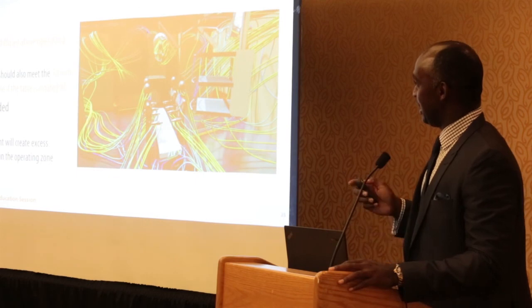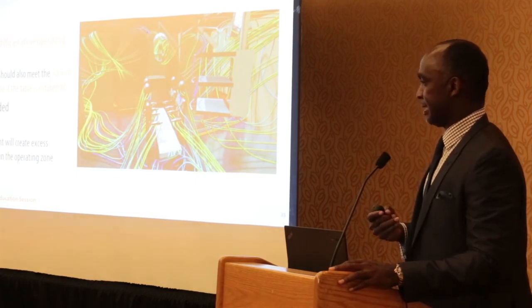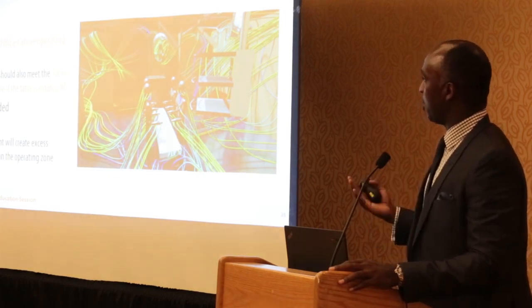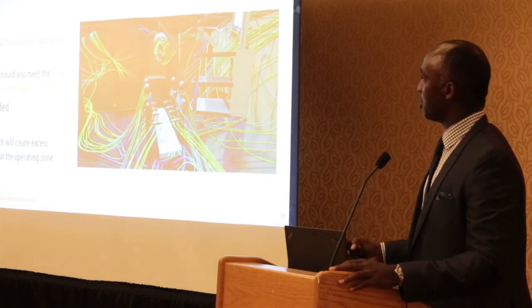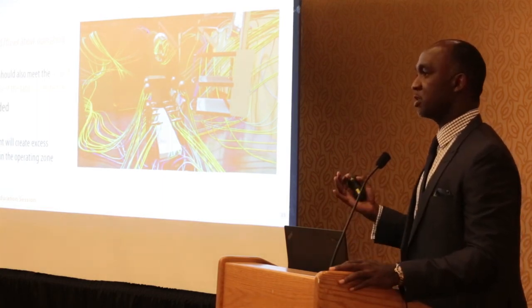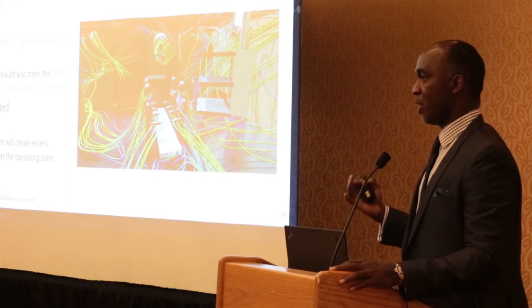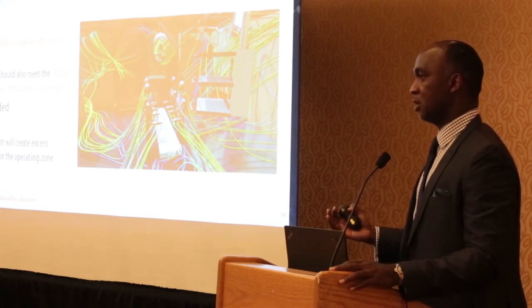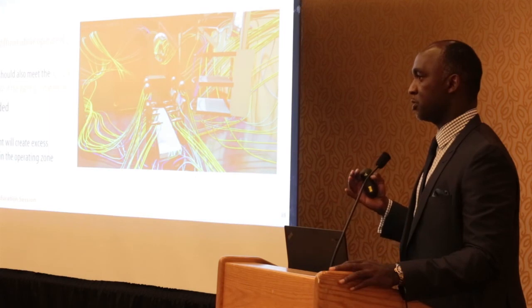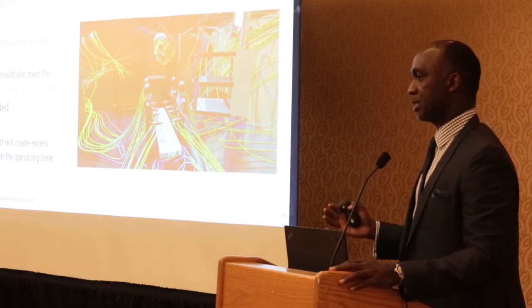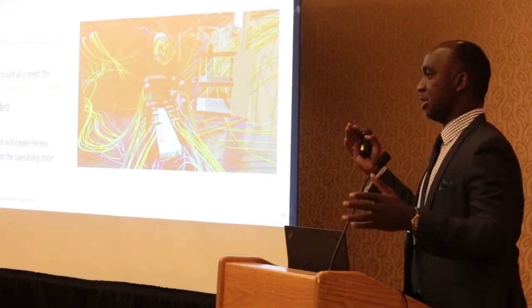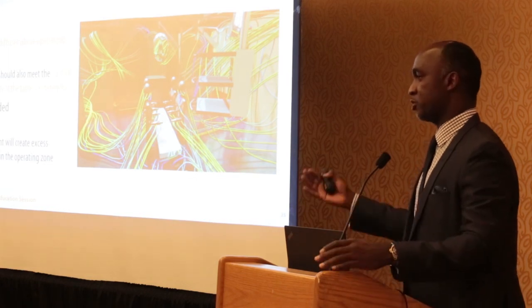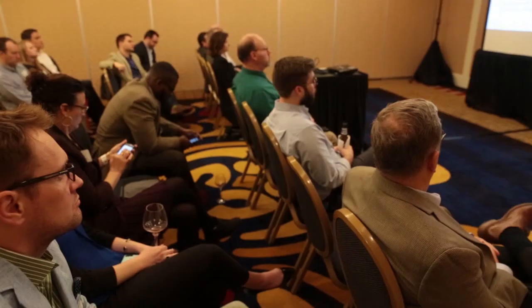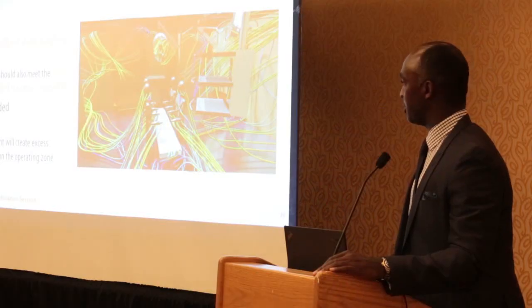And as a designer at Smith Group, what we do is recommend full laminar diffusers for these spaces, because they have so much equipment that when you have high velocity flows in those spaces, there's so much directional flow occurring that you have too much incidental air and air entrainment affecting your operating zone. So it's recommended that you have a full laminar ceiling when you're doing your hybrid ORs.